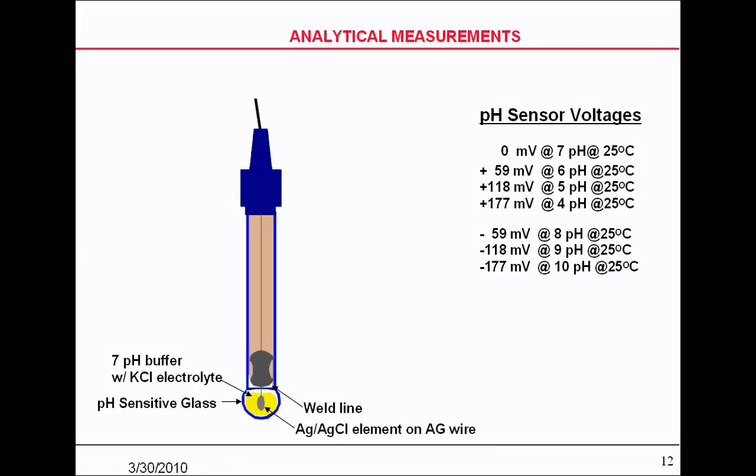You get a positive 59 millivolts at 6 pH, and negative 59 millivolts at an 8 pH, and 118, 177 as you change pH values. But those are always true at 25 degrees C.